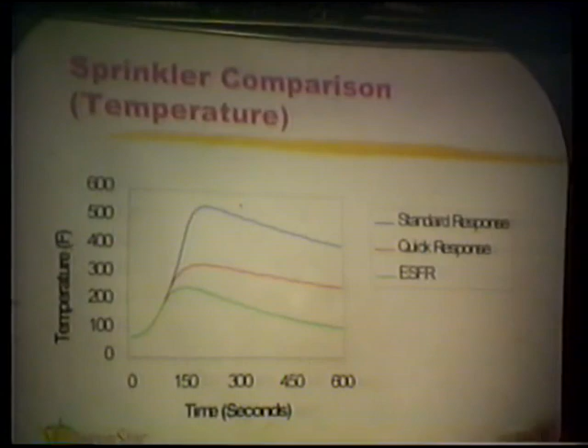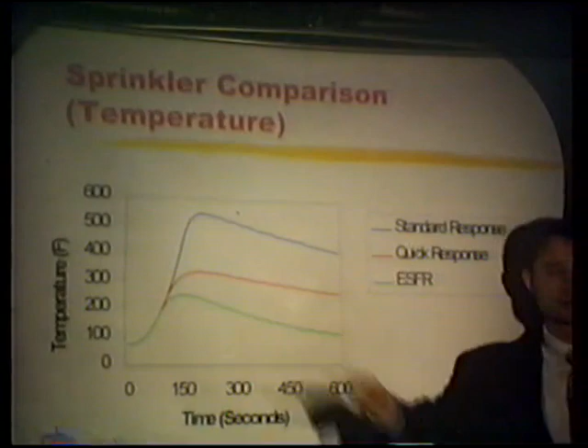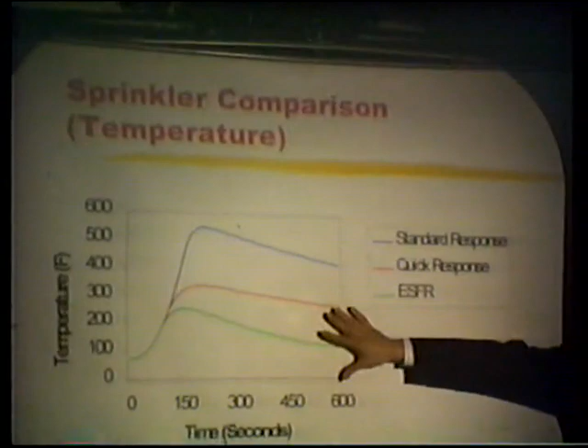Again, what we're showing is what's already been shown in a lot of fire test data, but we don't have to go out and set up a fire test to prove it. We can approximate, and intuitively it tells us quick response sprinklers will go off faster than a standard sprinkler, and subsequently, if everything's designed right, will hit the fire before it grows to a certain size, and the temperatures will be lower. That's what this is showing. You know that intuitively. Now we have tools that can approximate this and put the temperatures in quantitative terms.